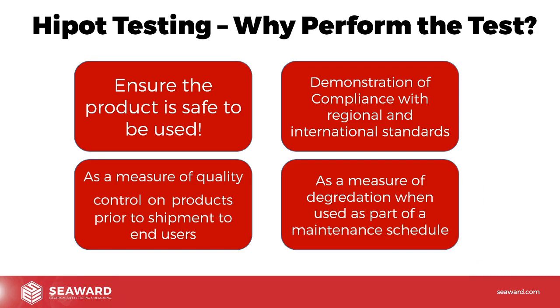And finally, we can also use it as a measure of degradation. If we are using the Hipot test in one of its applications, which would be a routine, ongoing test after repair or after use, we can start to log and record the leakage currents. As they start to creep up, we know that something's going wrong. We can decide to do something about it as part of our maintenance schedule before it becomes an unsafe piece of equipment.